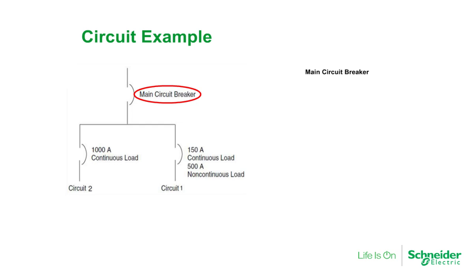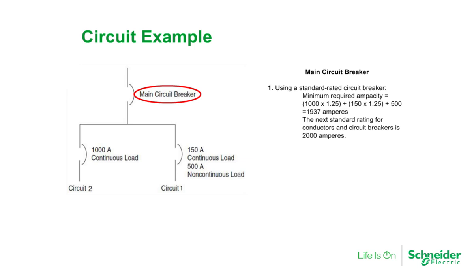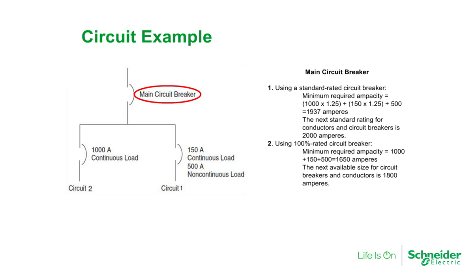Finally, let's take a look at the main circuit breaker calculation. When using a standard rated circuit breaker, the minimum required ampacity would be 1000A times 1.25 plus 150A times 1.25 for all the continuous load downstream from the main circuit breaker, plus 500A for the non-continuous load, which yields 1937A. The next standard rating for conductors and circuit breakers is 2000A. When using a 100% rated circuit breaker, the minimum required ampacity would be 1000 plus 150 plus 500, yielding 1650A. The next available size is 1800A, resulting in project cost reductions — specifically savings in the price of the busway, switchboard bussing, and cable.